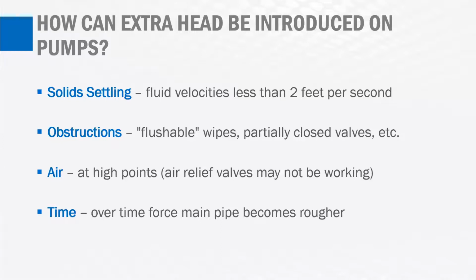Time is an issue. Over time, pipes simply get rougher than when they're brand new. And with that roughness comes higher friction and more head, more pressure on your pumps. So all of these things can be happening in your force main, and you may not even know it. Of course, you know that time is taking place, but a lot of these effects on the force main and subsequently on the pumps are really not looked at closely.